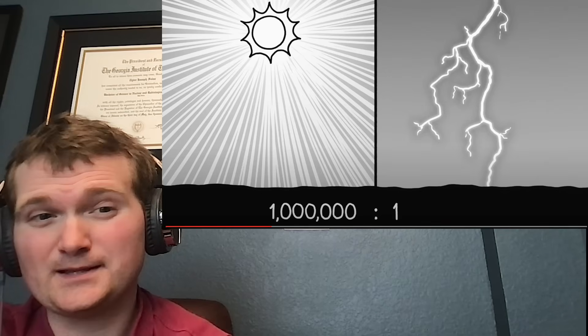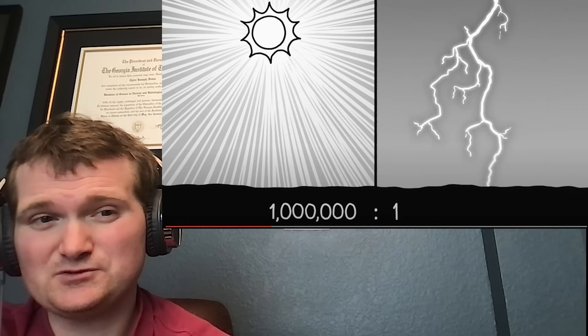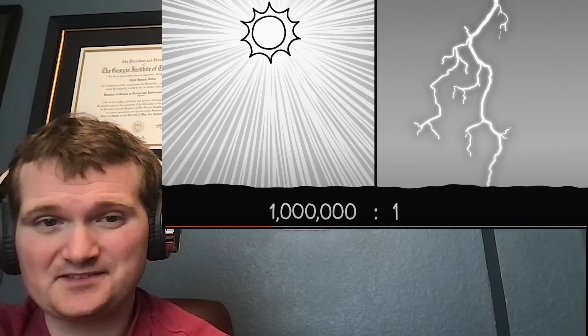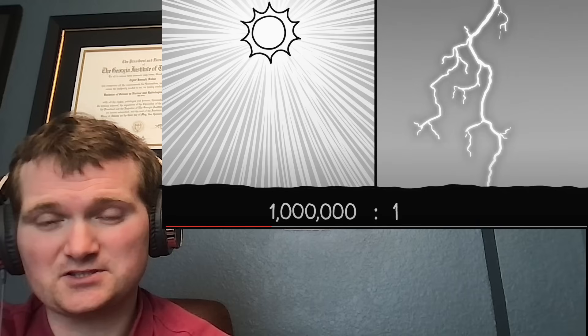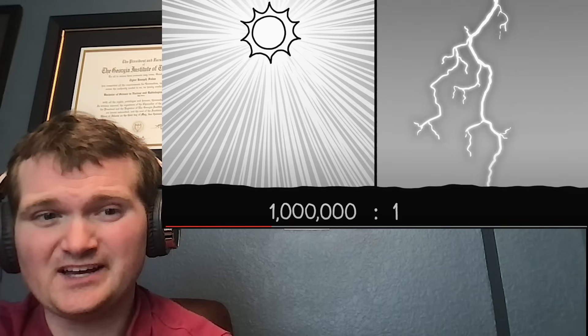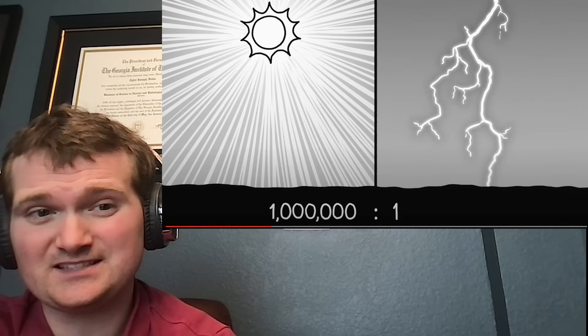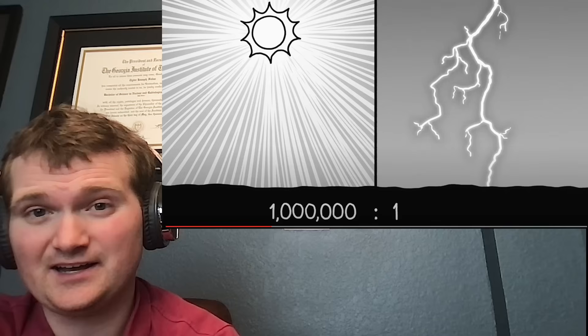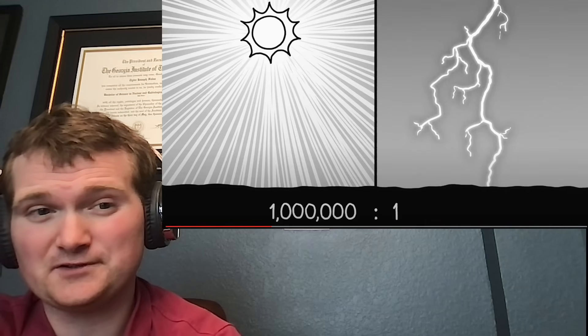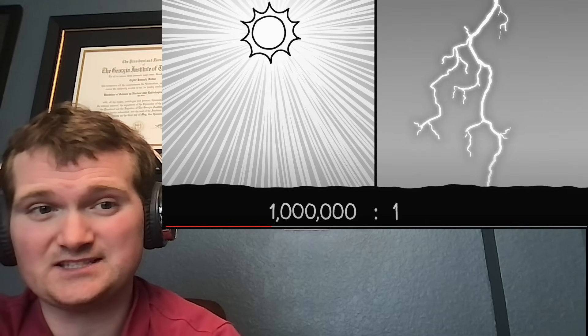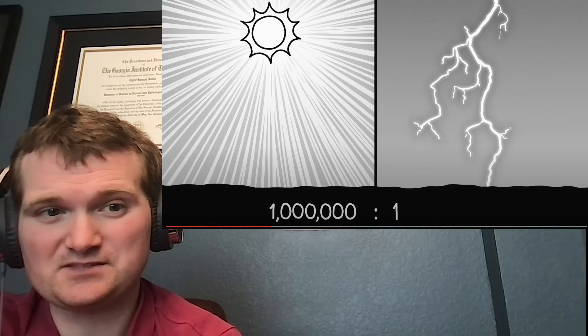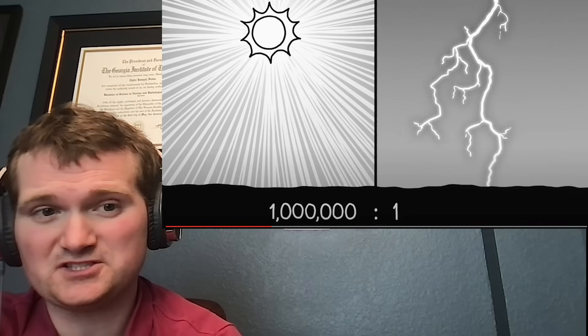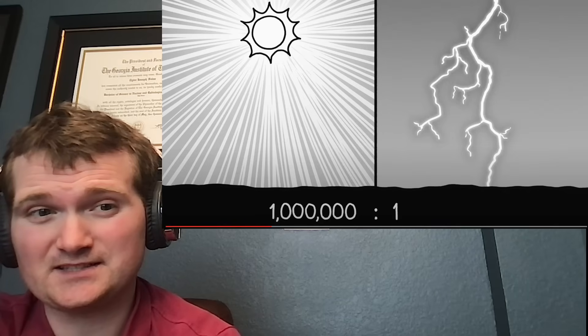Nuclear power plants invest a lot in their electrical protection. And if you do lose something, the electrical plant is set up that you don't lose large chunks of it at once. But even if you did, even if you lost the entire grid, there are backup diesel generators that can provide emergency power and uninterruptible power supplies. And keep in mind, these diesels, at least the safety-related ones, are actually located inside of structures. The diesel generator building is also a reinforced concrete structure, so the diesel itself isn't going to get struck by lightning. Not to mention, we have weather towers, meteorological towers, that can be used to predict where the severe weather and the lightning strikes are coming in.